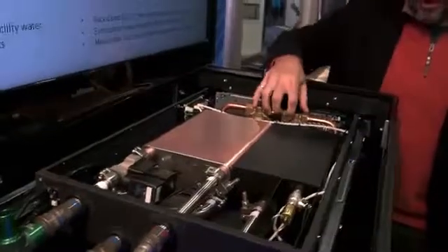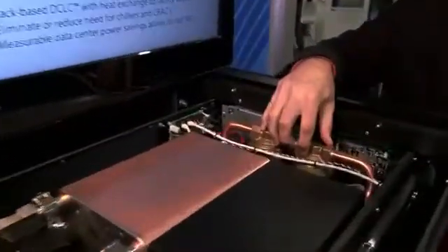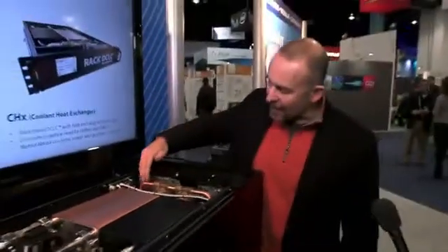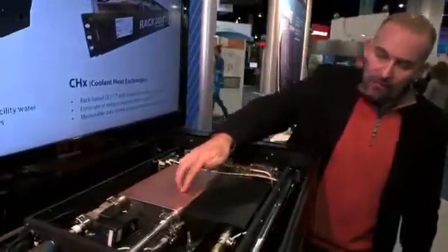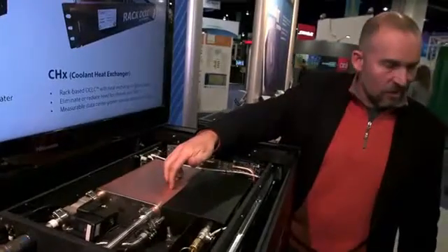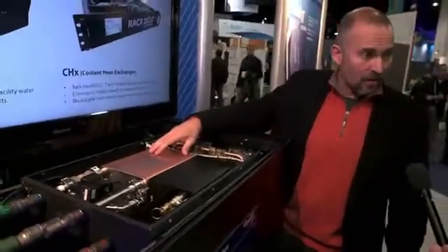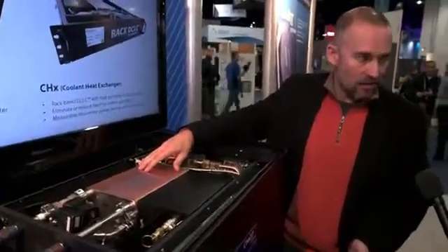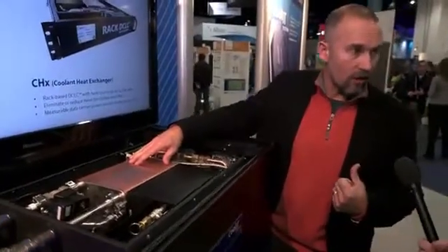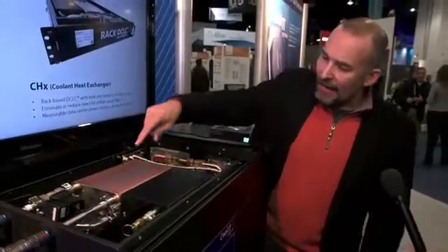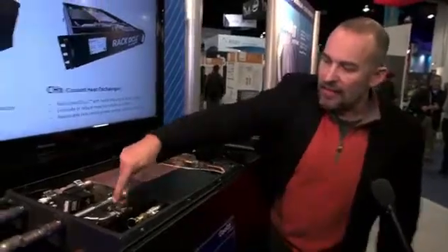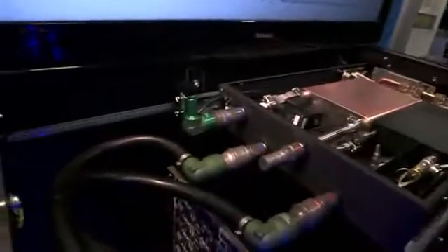Then we have our dual redundant circulating pumps. This is driving the flow for the entire rack. That hot liquid goes through the braze plate heat exchanger. This has a very high capacity, capable of dissipating tremendous amounts of heat, even more than what we're seeing here on the floor.